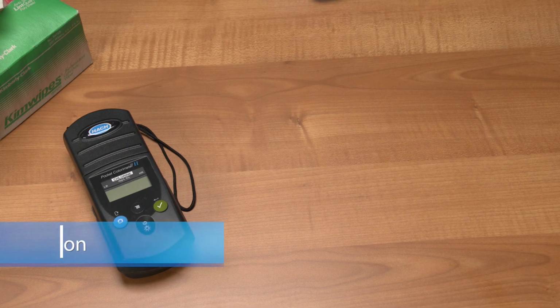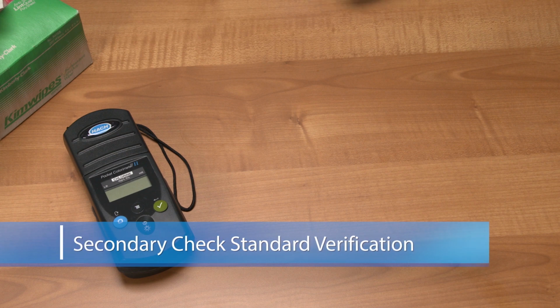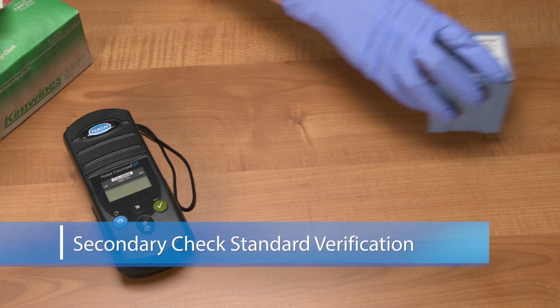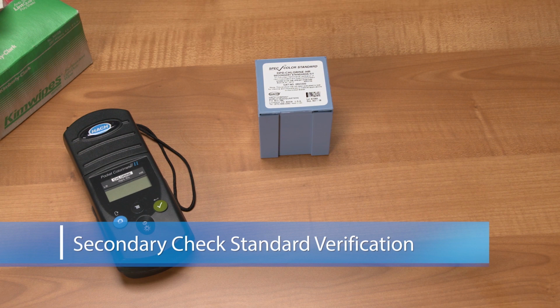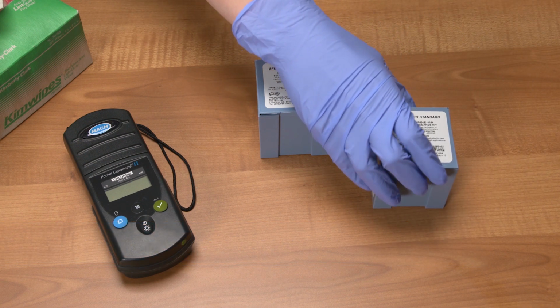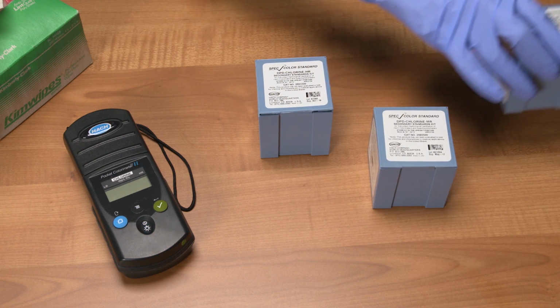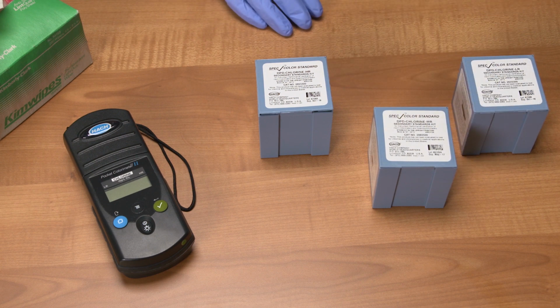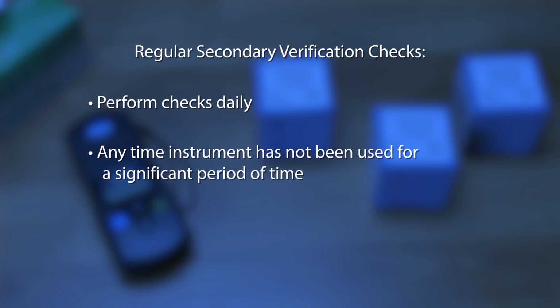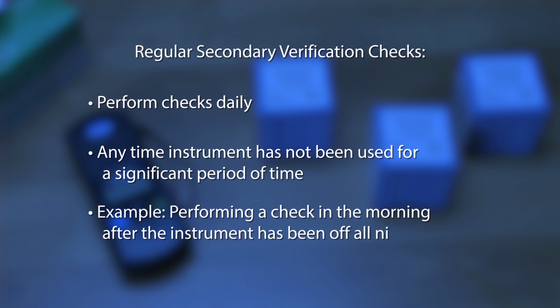Secondary check standard verification. It is a good idea to perform regular calibration verification checks with the secondary gel standards to verify that the colorimeter or spectrophotometer is operating properly. Analysis of secondary standards does not replace the analysis of aqueous check standards. It is a good idea to perform these checks daily, or anytime the instrument has not been used for a significant period of time. For example, performing a check in the morning after the instrument has been off all night.